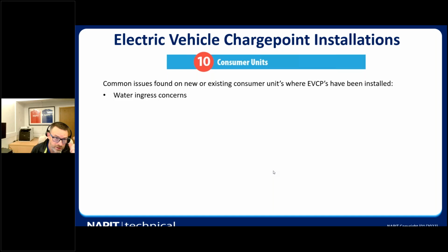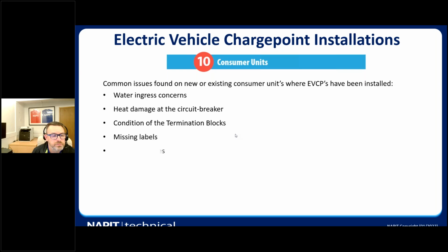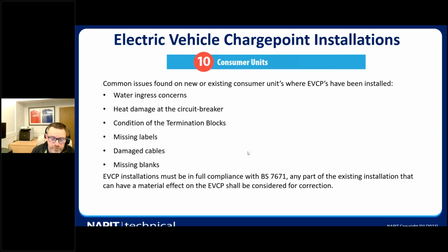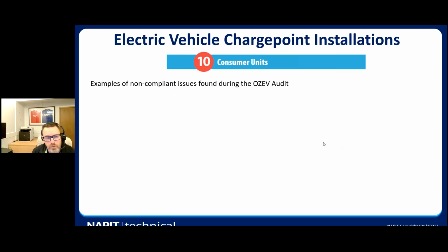Common issues found with the socket outlets, where we've got existing consumer units that have been installed, are water ingress, heat damage at the circuit breaker, condition of the termination blocks, missing labels, damaged cables, and missing blanks. An EV charge point must be in full compliance with 7671, and any part of the existing installation that can have a material effect on the EV charge point installation has to be considered for correction. When we're looking at installation, we must consider everything that must be corrected.